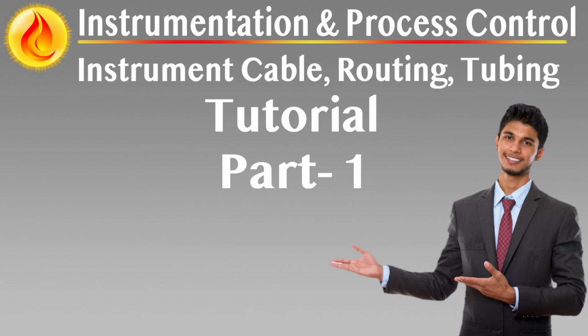Collective screening is standard. Individual pair screening is applied only when functionally necessary, such as in high-precision measurement loops or noise-prone areas. Cable construction must not invalidate the requirements of intrinsically safe or non-incendive circuits. Capacitance, inductance, and resistance must remain within limits that preserve safety barriers and system signal integrity. Underground cables should utilize AL-HDPE PA sheathing for combined moisture and chemical resistance.